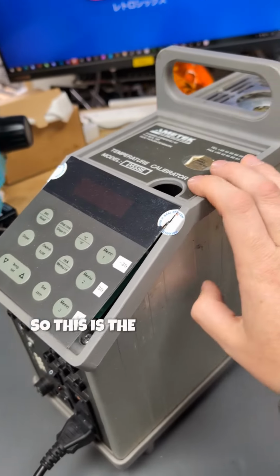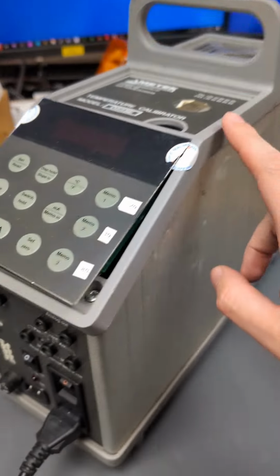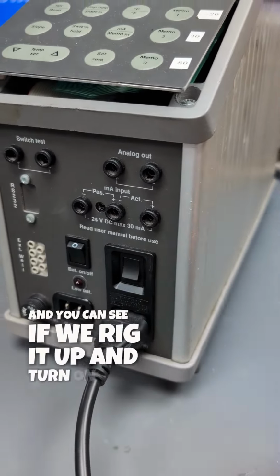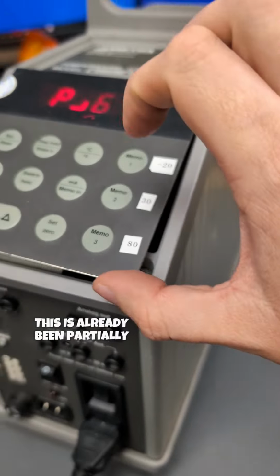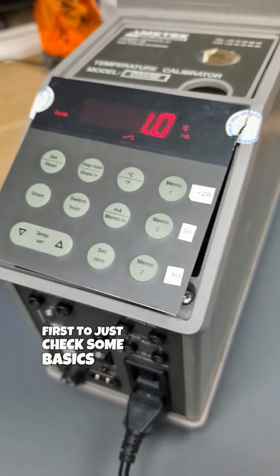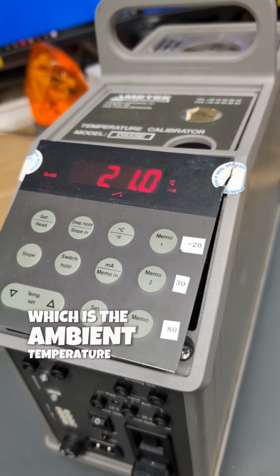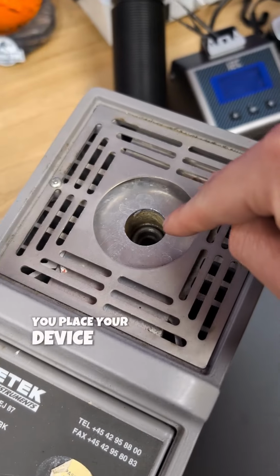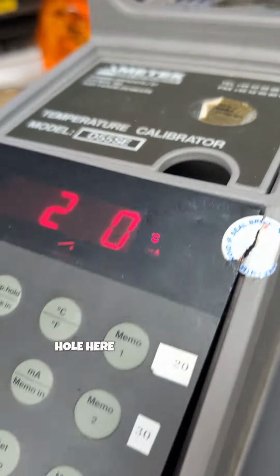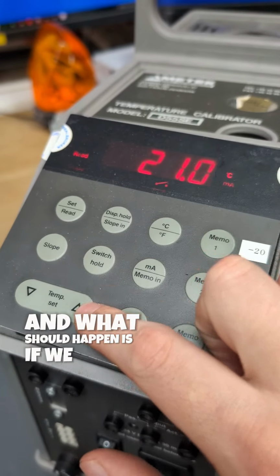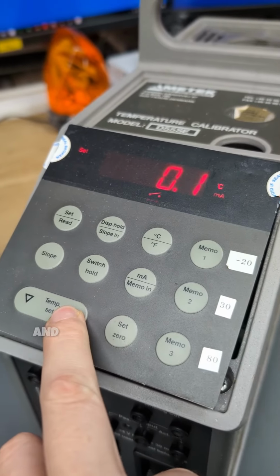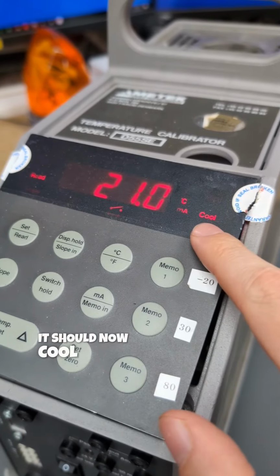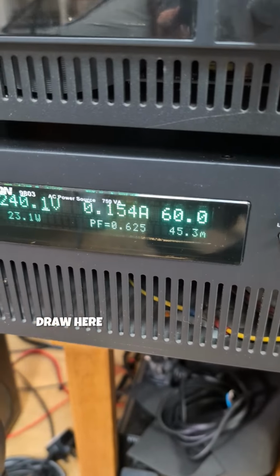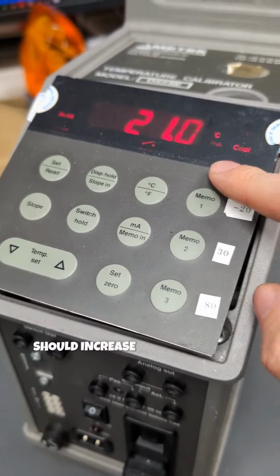So this is the temperature calibrator, also called a hot block. And you can see if we rig it up and turn on, this has already been partially opened by the customer first to just check some basics. We've got a temperature display, which is the ambient temperature in the room. You place your device for calibration testing in the hole here, and what should happen is if we select set and say set a temperature at almost 0, it should now cool down, and then this would change as it goes. Based on the current draw here, it's not doing anything because that should increase.